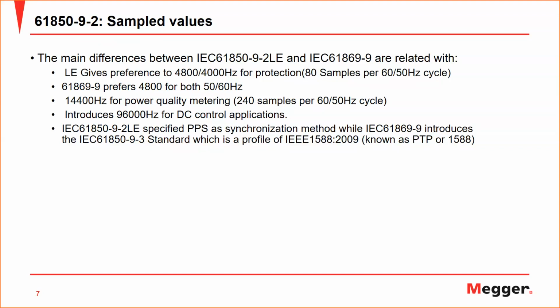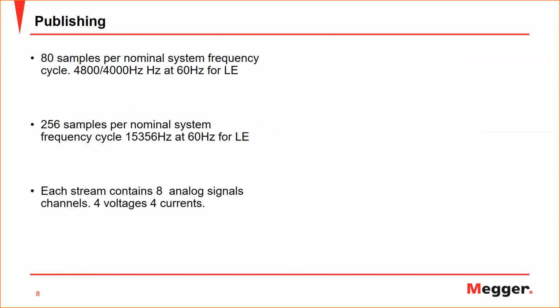So, this talk about the standard, can we simplify it? It's very simple. If we only take, for example, now just the light edition one, not the others, I will be having 80 samples per system frequency cycle. So 4,800 samples for 60 hertz and 4,000 samples for 50 hertz. Or a different profile also defined by the light edition is 256 samples.